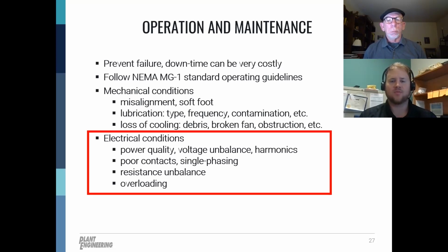If you do have a motor that's on a contactor, which in most cases it is, make sure you're keeping an eye on those contactor terminals. You may have carbon or contaminant buildup, especially if it's like a conveyor or press application where you're turning off and on. So you may have the contactor opening and closing a lot. So keep an eye on that. Keep an eye out for contactor pitting also over time.